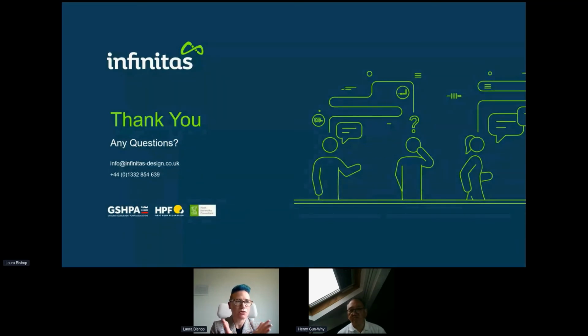But will the cost come down? I should also say there is software out there that should definitely be used, especially if you're retrofitting a heat pump. Software like HySopt will do your hydraulic modelling, and you can do your what-if analyses, turning down temperatures, changing delta T's, changing pump speeds and things like that. So I'd recommend that whether you're doing a gas boiler or a heat pump, to be honest.